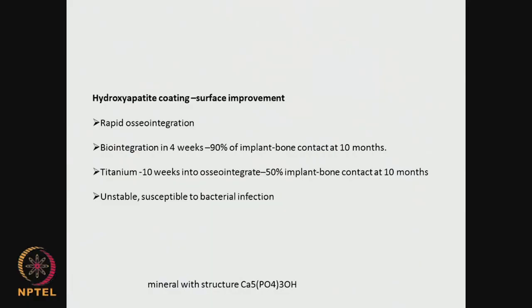Hydroxyapatite coating — this is an inorganic material. It improves the surface property and helps for osteointegration. For example, if you use stainless steel it is very inert and the bone cells do not integrate. Whereas when coated with hydroxyapatite, it helps in osteointegration. There is an example: 90% of the implant gets biointegrated with the bone in 10 months contact. Whereas with pure titanium without any HA coating, only 50% of the implant makes contact in 10 months. Hydroxyapatite is much better.